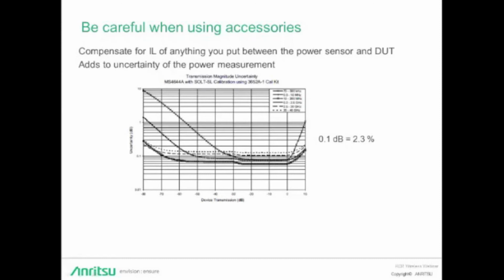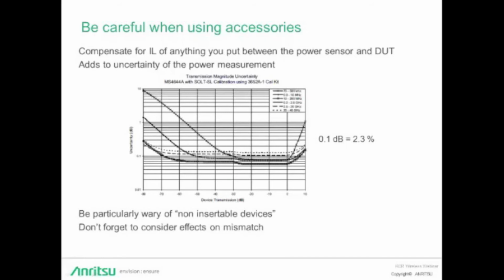Even when making an insertion loss measurement on a high precision vector network analyzer like the Anritsu VectorStar VNA, you can still easily add 1/10 of a dB of uncertainty to the power measurement. Be particularly wary of non-insertable devices, as they're difficult to measure and the associated uncertainty is difficult to estimate. A non-insertable device means that an adapter is required to connect the DUT to the power sensor. As mentioned previously, mismatch can have a very significant effect on power measurement uncertainty. And just don't forget to consider the effect of any accessory added to the adapters on mismatch.